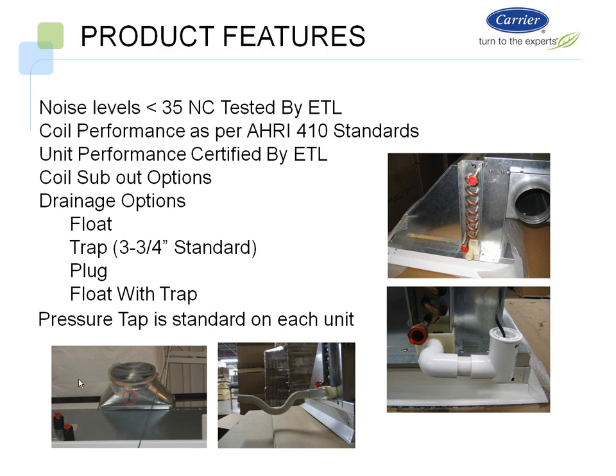So let's say you're in that sensible only scenario, that application, and you do have one by an exit door, and you don't mind that it's going to drain a little bit. Oh boy, when that door is open, maybe we'll get an eighth of an inch or a quarter of an inch of some water in there. So I don't want to shut off the flow to this unit, right? So you can actually set that switch to where you need it to be, so that if it rises above that point, then it'll shut the valve off.